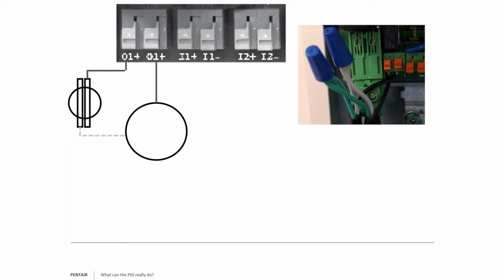Now here we show the wires. Now the first thing, whenever you're wiring a light, for example, in this case I'm using a trouble light, I always first connect my grounds together. So I have my cord I'm plugging in, or I'm pulling it off of a power supply. I'll do my grounds first. As an electrician, you should always be working with electrical. Start with your ground. Second thing you would then hook up is your neutrals, okay, because that helps keep you safe. Then your two black wires, your black wire coming in from your power supply goes into the relay.